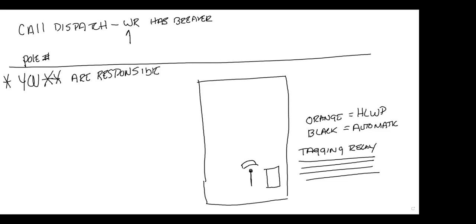Now, overload. What is breaker overload? Pulling too many amps or pushing out too many amps? No, whatever the piece of equipment is, conductor, transformer, fuse, you've gone over the limits of amps load on that piece. So if I said yesterday, if I've got a 20 amp fuse, let's go ahead and do a little math here. It will go to 150%. So it will do 30 amps for a short period of time. Well, what's wrong if it does 40?